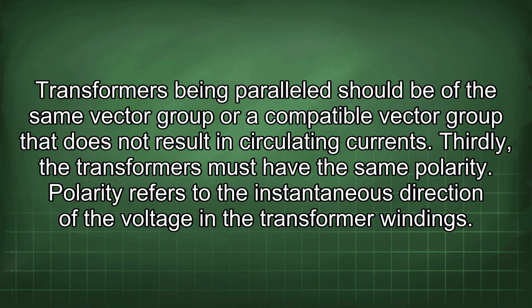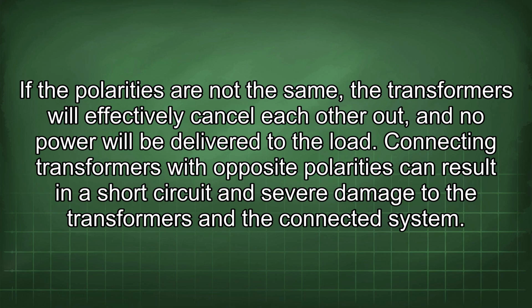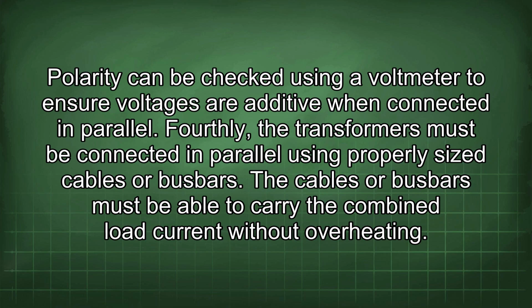Thirdly, the transformers must have the same polarity. Polarity refers to the instantaneous direction of the voltage in the transformer windings. If the polarities are not the same, the transformers will effectively cancel each other out, and no power will be delivered to the load. Connecting transformers with opposite polarities can result in a short circuit and severe damage to the transformers and the connected system. Polarity can be checked using a voltmeter to ensure voltages are additive when connected in parallel.